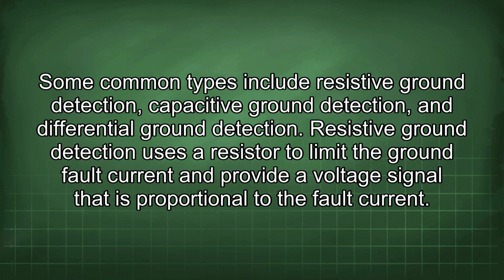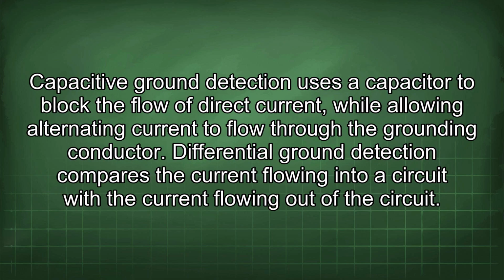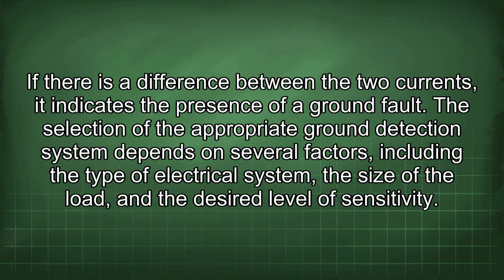Resistive ground detection uses a resistor to limit the ground fault current and provide a voltage signal that is proportional to the fault current. Capacitive ground detection uses a capacitor to block the flow of direct current while allowing alternating current to flow through the grounding conductor. Differential ground detection compares the current flowing into a circuit with the current flowing out of the circuit. If there is a difference between the two currents, it indicates the presence of a ground fault.